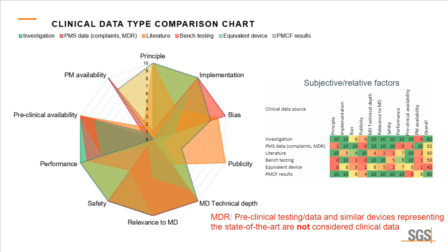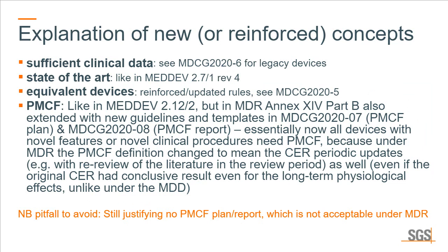types of clinical evidence. It's also important to point out that in the MDR, preclinical testing and data and similar devices representing the state of the art are not considered clinical data. So again, the definition has been clarified a little bit. I talked already about sufficient clinical data. There's an MDCG guideline that talks about sufficient clinical data for legacy devices. Legacy devices for our practical purposes now will mean MDD certified devices or AIMDD certified devices.